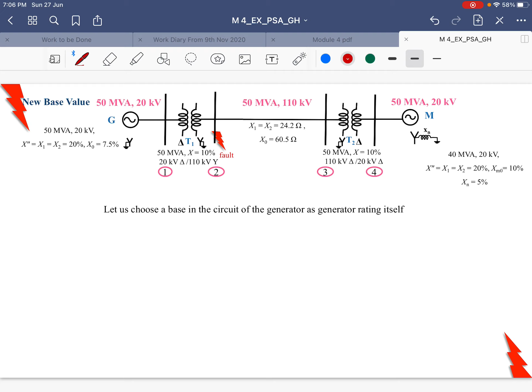That is, the base MVA remains the same everywhere and the base kV is calculated based on the transformers in between. Now I have to convert all positive, negative and zero sequence reactances of all the machines here. Therefore, I will start with the generator. For the generator there is no necessity of calculating, because the base quantity is 50 MVA, 20 kV and the rating of the machine is also 50 MVA, 20 kV. Therefore, all values remain the same. So x1 is equal to x2 is equal to 0.20 for the generator, and x0 is 0.075.